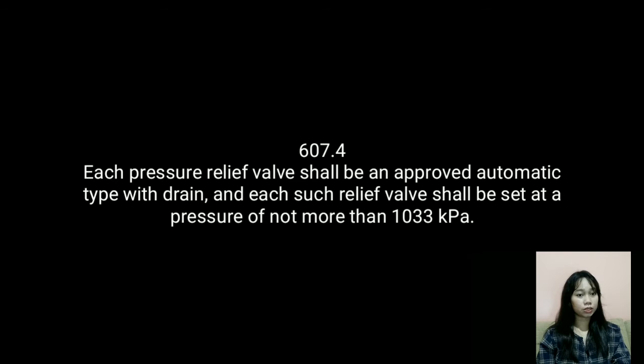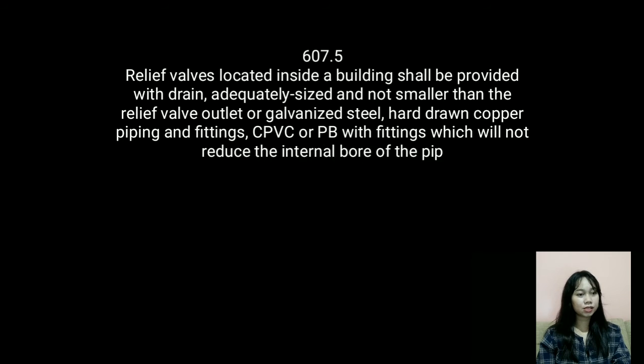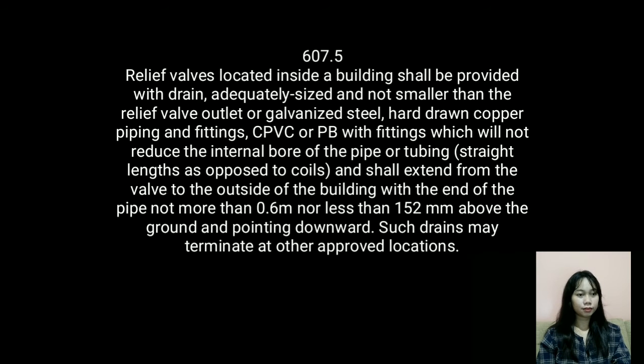Section 607.4: Each pressure relief valve shall be an approved automatic type with drain. Each such relief valve shall be set at a pressure of not more than 1,033 kilopascals.